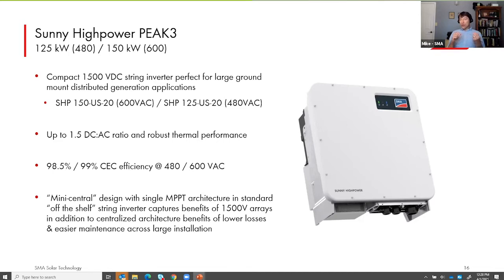The 600 volt, 150 kilowatt unit has a 99% CEC efficiency. So that's not a peak efficiency, that's CEC weighted efficiency over lots of loading ranges, lots of voltage ranges, 99% efficiency. So designed for that high efficiency, the benefit of 1500 volt strings, long strings, so fewer strings in parallel in the combiner to the inverter for the same power, with an off-the-shelf device, very easy to source and place.